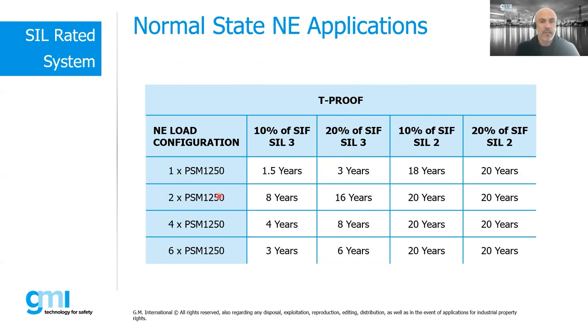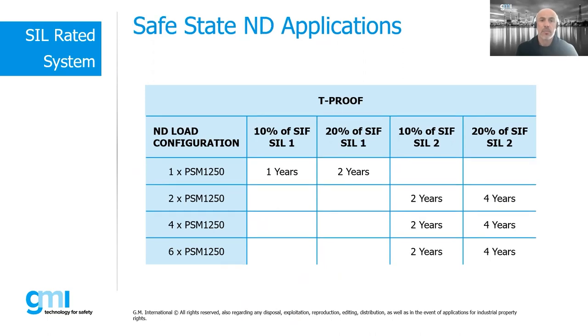While if you use two power supplies, the second line, you increase the proof test interval considerably, to 8 years and 16 years for 20% of the SIF. So basically, as you can see, if you're using the power supply for SIL2 loops, you can use it for the whole installation lifetime without testing. While if you use more power supplies connected, you of course increase the availability, but the safety is decreased because you need more testing than with two power supplies. That's for normally energized. For normally de-energized, it is completely different.